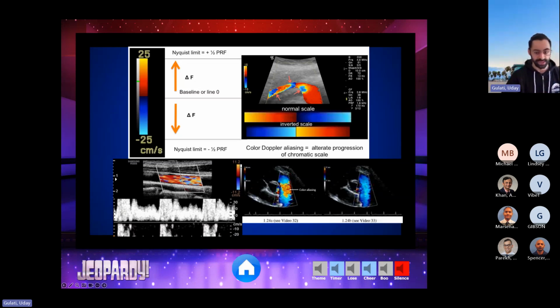So it looks like there's really bad AS, but really it's just that you have to change the settings of the machine to allow it to pick up higher speeds, higher velocities. And so have some caution about that, right? Because you'll misinterpret your final diagnosis when really it's just a normal patient, normal velocities. And so I would definitely build up an understanding of the terms that you guys should be aware of, like pulse repetition frequencies, Nyquist limits, and then aliasing.